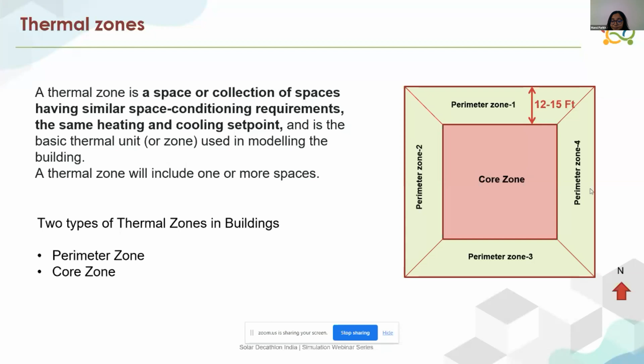In the core zone, the impact of internal loads is very high compared to the perimeter zone, where external loads driven by climatic parameters are higher. These thermal zones are used for indoor HVAC system sizing, such as VAV systems or cassette units, where each space has its own indoor unit. For example, perimeter zone 3 facing south might require 2.2 tonnage of refrigeration, while the indoor unit in the north might require 1.8 TR, and the core zone might require 1.5 TR. This is an assumption and would vary case to case, but there's definitely a difference depending on whether external loads are predominant in a particular space or building type.